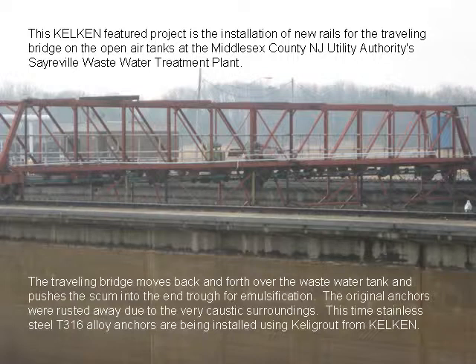The original anchors were rusted away due to the very caustic surroundings. This time, stainless steel T316 alloy anchors are being installed using Keligrout from KELKEN.